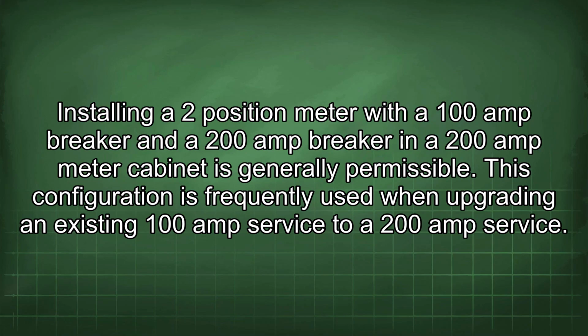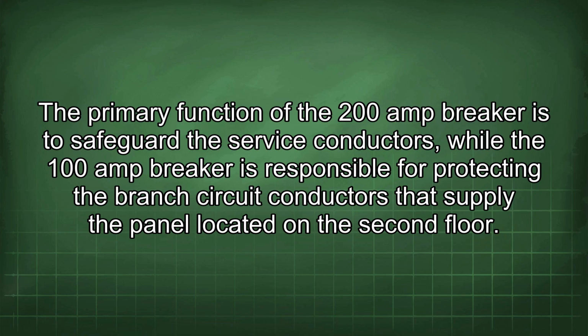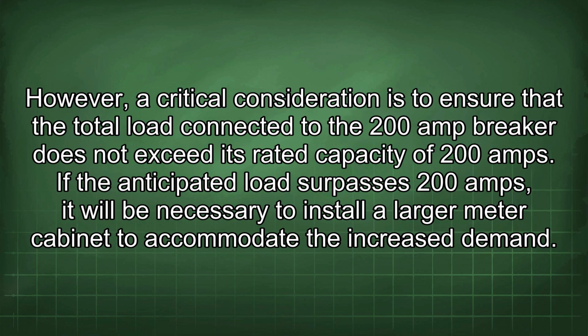Installing a 2-position meter with a 100 amp breaker and a 200 amp breaker in a 200 amp meter cabinet is generally permissible. This configuration is frequently used when upgrading an existing 100 amp service to a 200 amp service. The primary function of the 200 amp breaker is to safeguard the service conductors, while the 100 amp breaker is responsible for protecting the branch circuit conductors that supply the panel located on the second floor. However, a critical consideration is to ensure that the total load connected to the 200 amp breaker does not exceed its rated capacity of 200 amps.